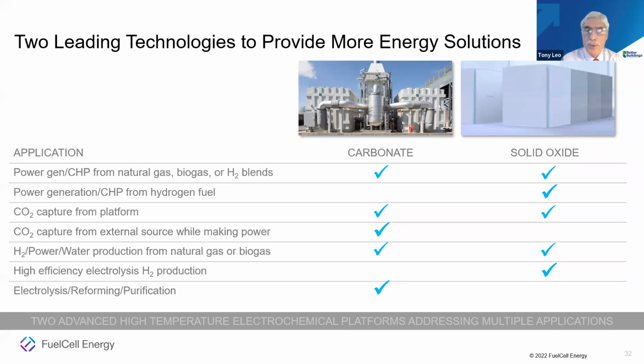Solid oxide can run on pure hydrogen fuel. Carbonate needs a blend of hydrogen and natural gas if you want to use hydrogen, because the carbonate chemistry needs some CO2 in an internal recycle system. Both technologies are amenable to capturing CO2 from their own platform. If you fuel these fuel cells with natural gas, at the point they convert methane to hydrogen and produce CO2, that CO2 hasn't yet mixed with air, so it's easy to extract what would otherwise be emitted.